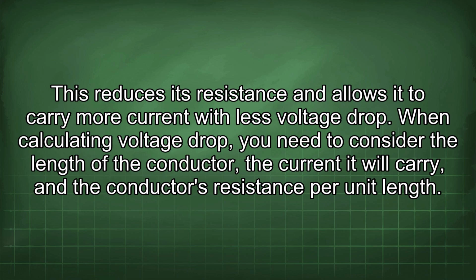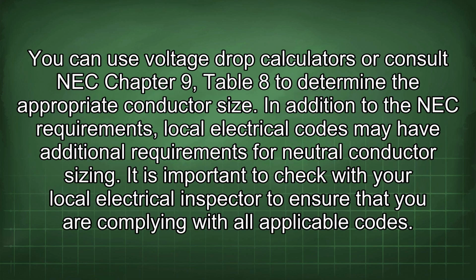When calculating voltage drop, you need to consider the length of the conductor, the current it will carry, and the conductor's resistance per unit length. You can use voltage drop calculators or consult NEC Chapter 9, Table 8 to determine the appropriate conductor size. In addition to the NEC requirements, local electrical codes may have additional requirements for neutral conductor sizing. It is important to check with your local electrical inspector to ensure that you are complying with all applicable codes.